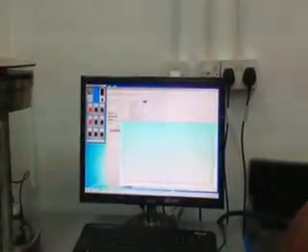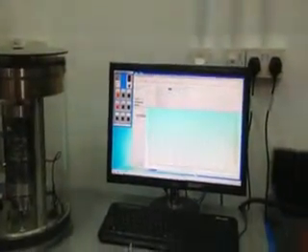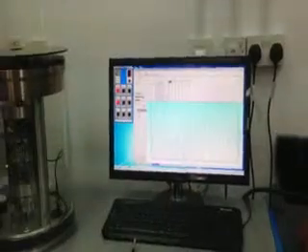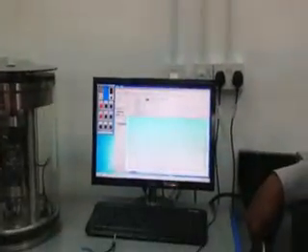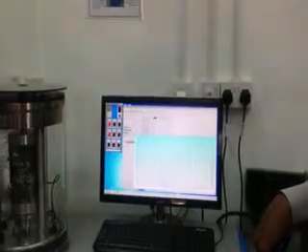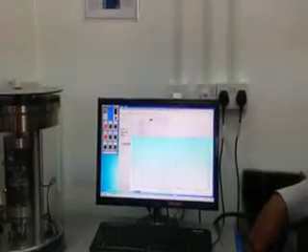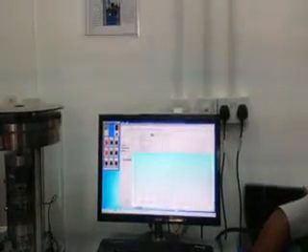In general, on all hydraulic tests, where do we select the low condition? Probably for indirect tensile testing. Tensile testing is low, so we select low conditions. For the AMPT, it's always high. Depending on the test, an indirect tensile test takes a lot less load to apply than loading on the top of the sample. As you do more testing, you'll get familiar with whether to run high pressure or low pressure.